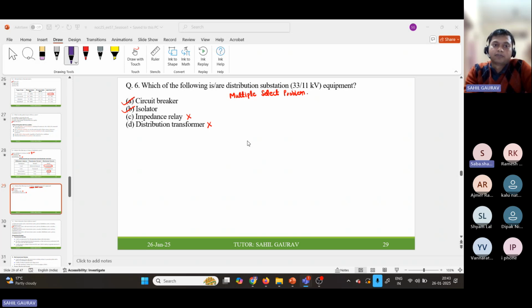Is the distribution transformer secondary voltage always 440 volts, sir? Three phase? 400 volt, not 440 volt. Yeah, that is the utility voltage. So the secondary side should have 400 volt. Only if the secondary voltage is 400 volt will it be called a distribution transformer.